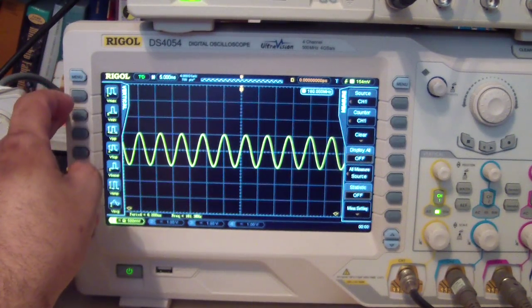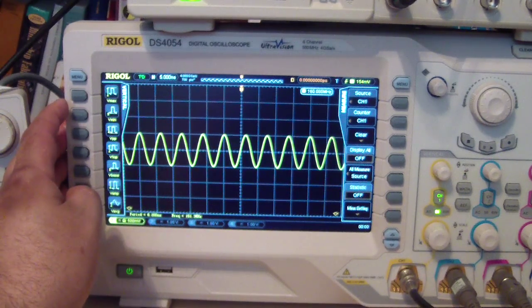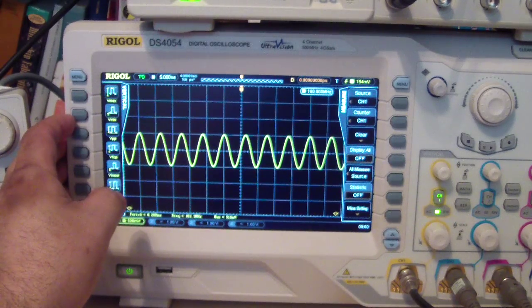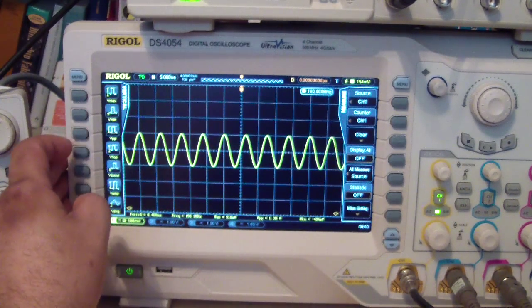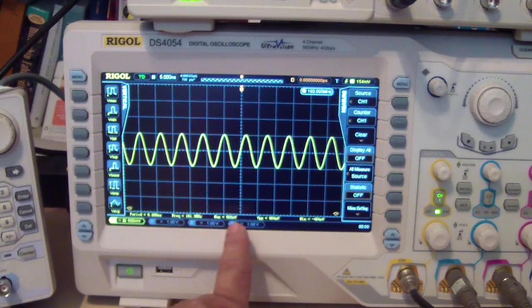If you press it again, you get a vertical menu, which is voltage related. So in this case, let's say Vmax, Vmin, peak to peak. Okay, so it displays my period, my frequency, max, peak to peak, and min. So those are the 4 measurements that you can take.